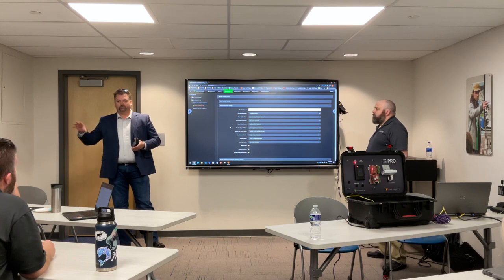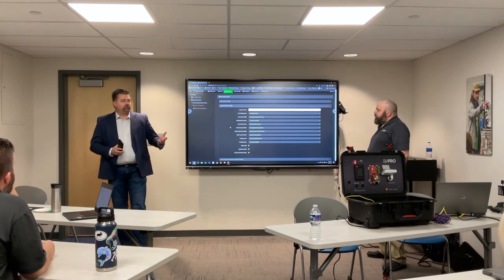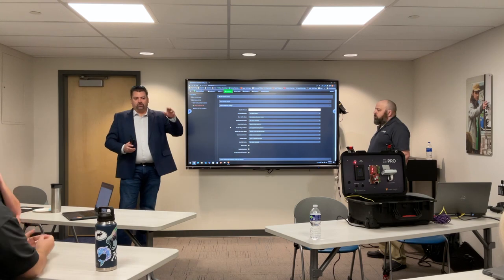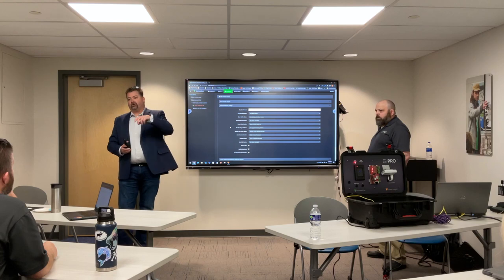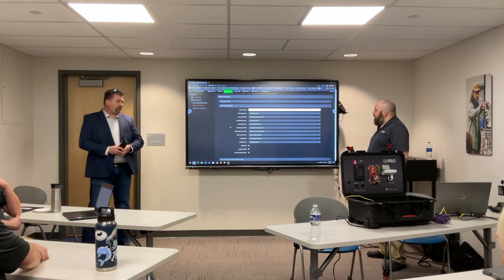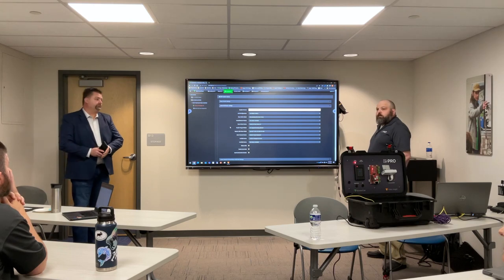In your older schools, if you're using Wiegand, you can still use Wiegand and OSDP together. I already do that at 27J. They use LP1501s everywhere just because they want to, which is okay, great. They put them in and they do all that stuff. So they can do OSDP on the new schools, and if they have something that fails, they can just keep their door hardware in place, which is Wiegand, and keep that going forward. And I think the new readers do both protocols. So if you have an old Wiegand card, it'll work on an OSDP reader. So, sorry.